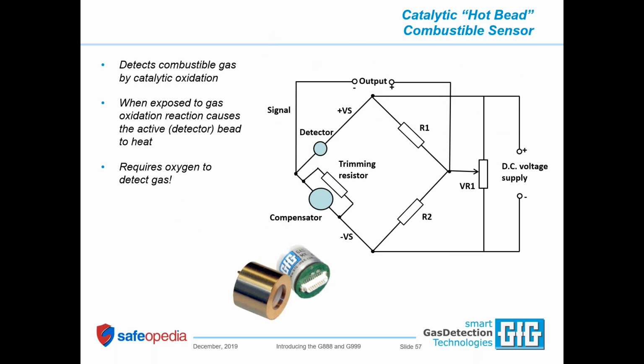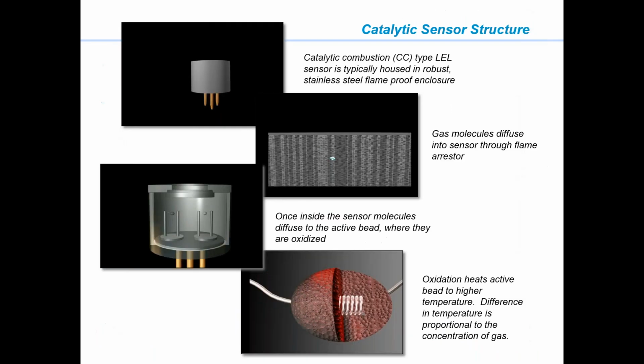They are still the best choice for a lot of the smaller hydrocarbon gases. Anything between methane and pentane, even up to hexane, a standard catalytic sensor is a good choice. It's a particularly good choice if you need to measure acetylene in LEL ranges. So no bad mouthing of the catalytic LEL sensor, but that's not where we stop.